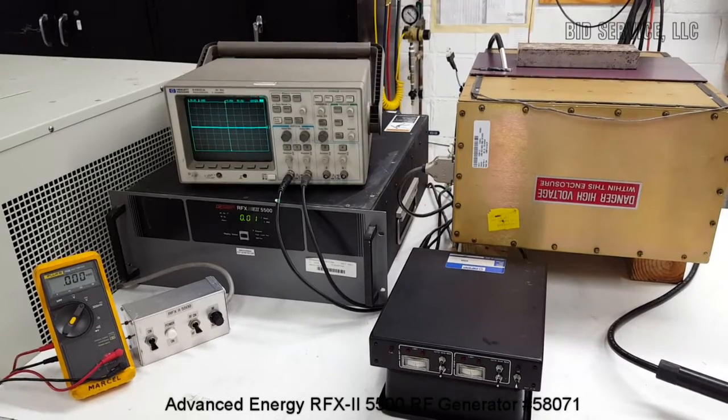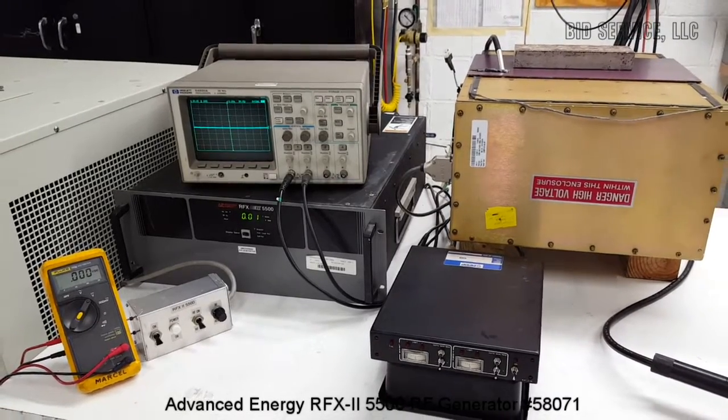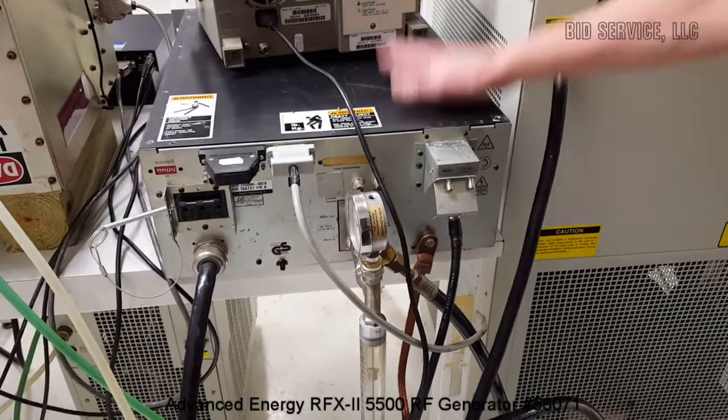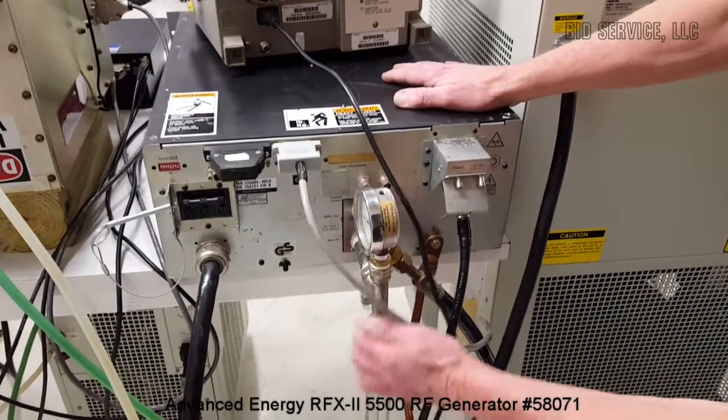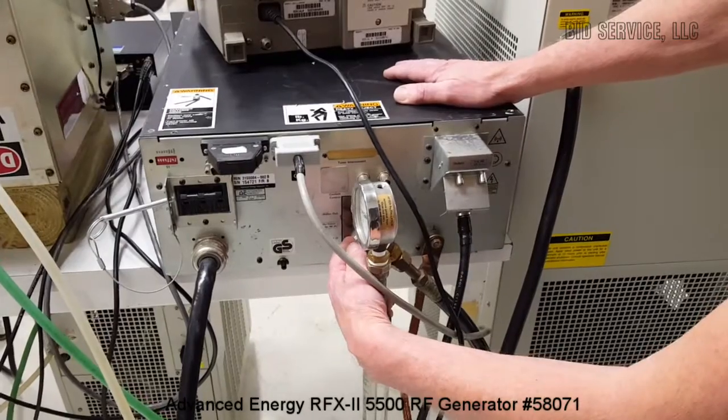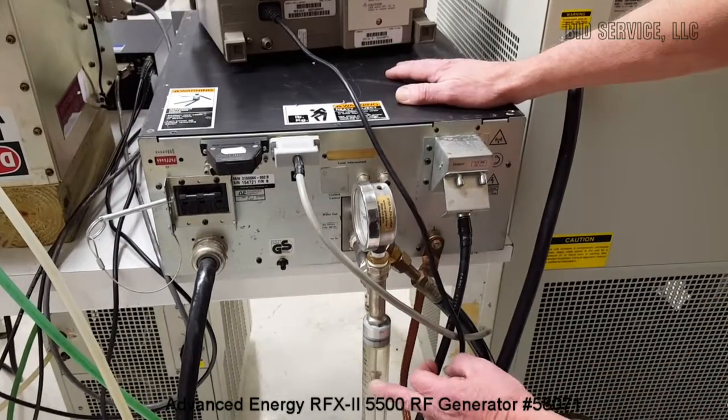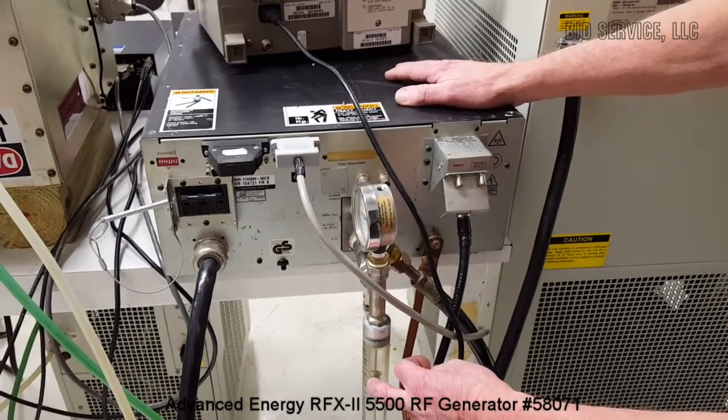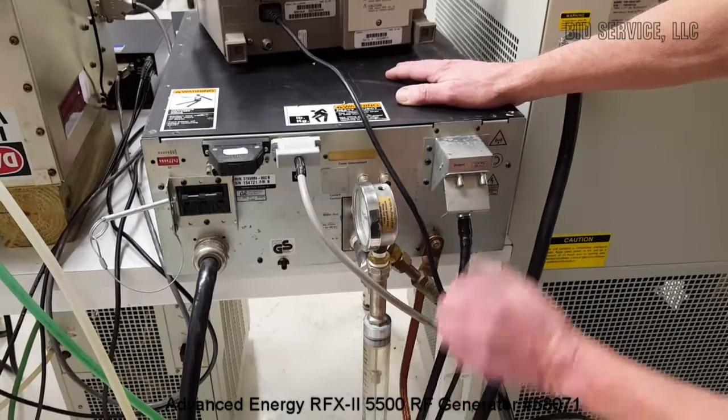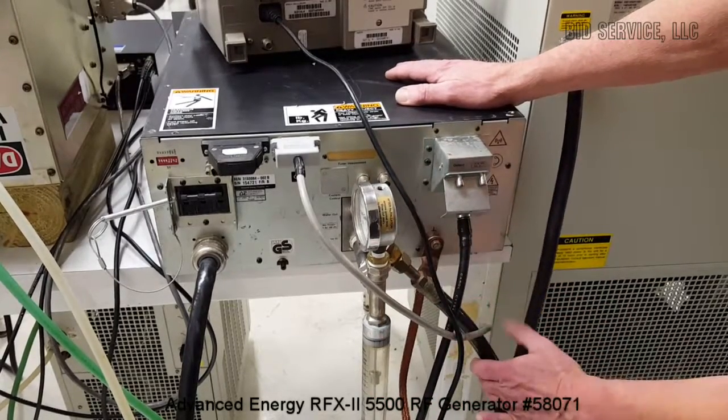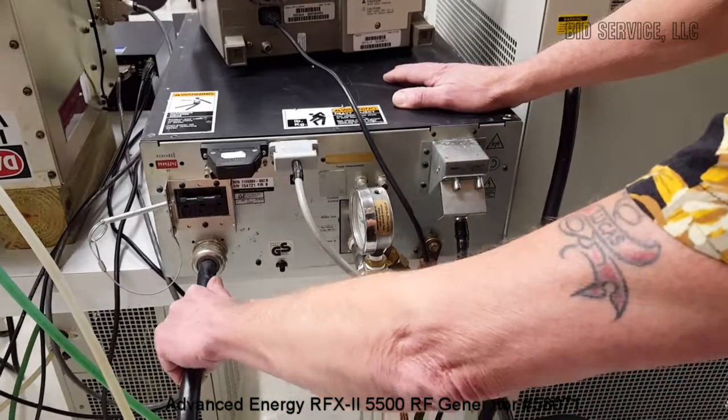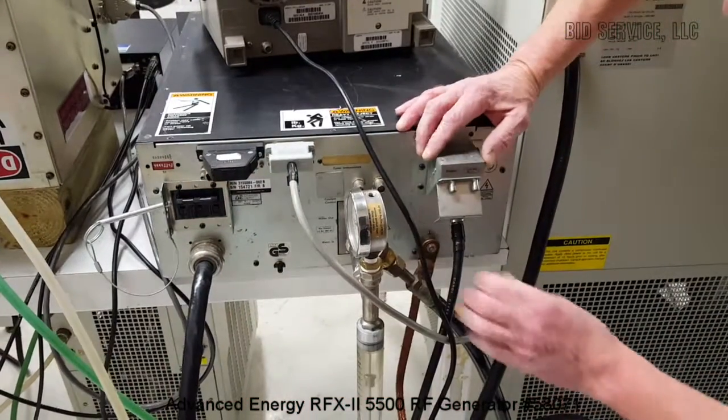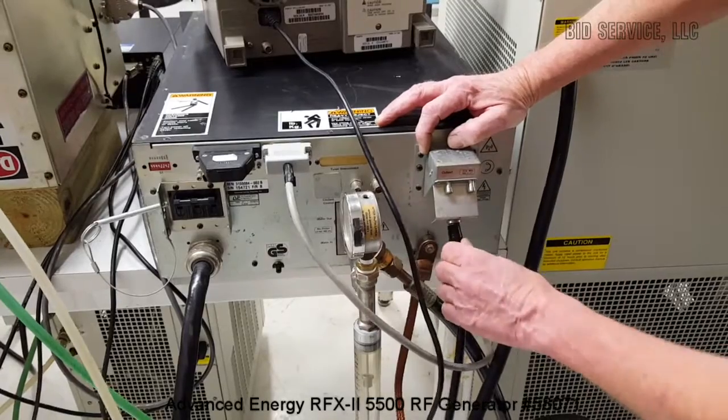Now let's take a look at the connections in the back. The connections on the RF generator are as follows. Here's where we have our water line going in. Our flow gauge says 4.5 gallons per minute, which is acceptable. This is the return line for our water to our chiller. Here is our power connection and here's the actual RF output plug underneath.